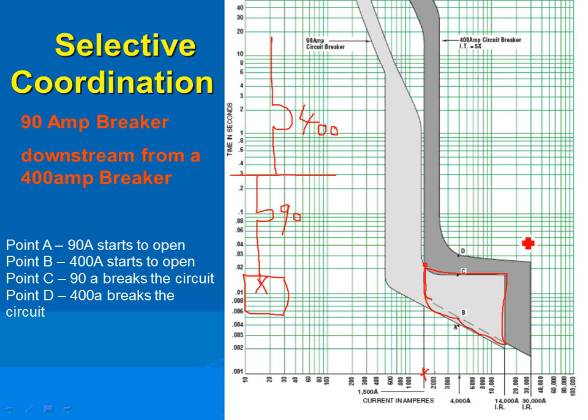So 90%, and I would dare to say 96 to 98% of the time, guys, you have full coordination. 95% of the time you're going to be in this range. So the 5 to 4% of the time, all hell breaks loose, and it's the rest that you're going to have. Granted, most of your ground faults, which is the most offender, guys, 85% are ground faults. All your ground faults are right here in this area. These are only when you have phase to phase or phase to phase to phase. That's when you are in this area.